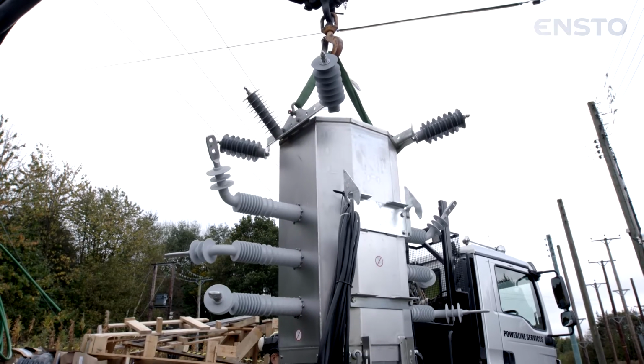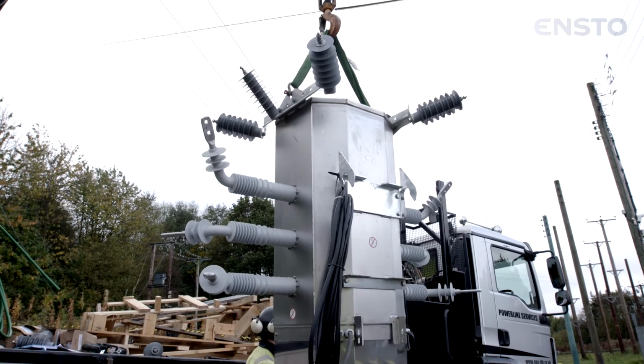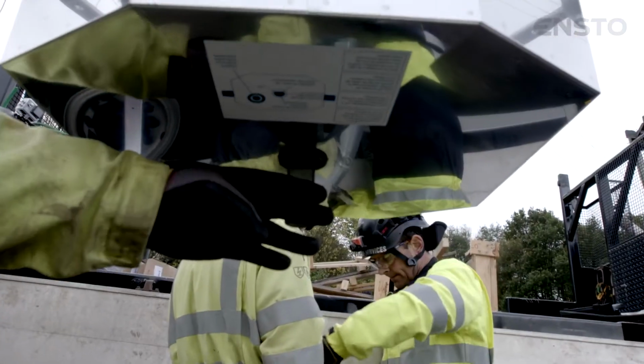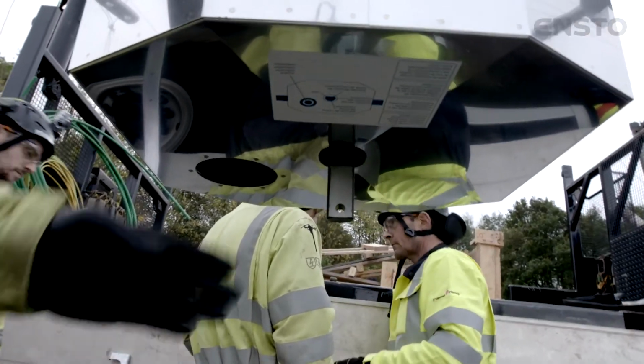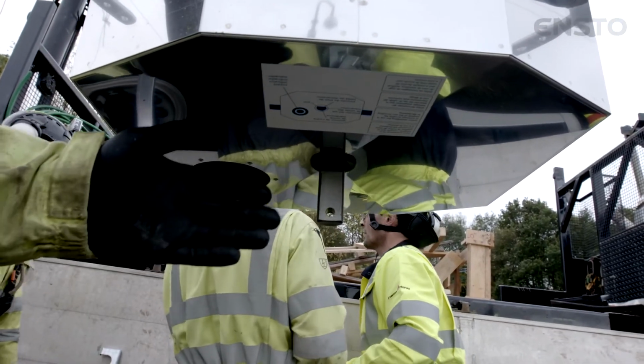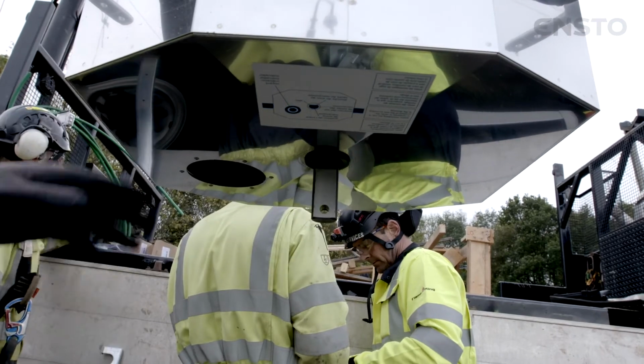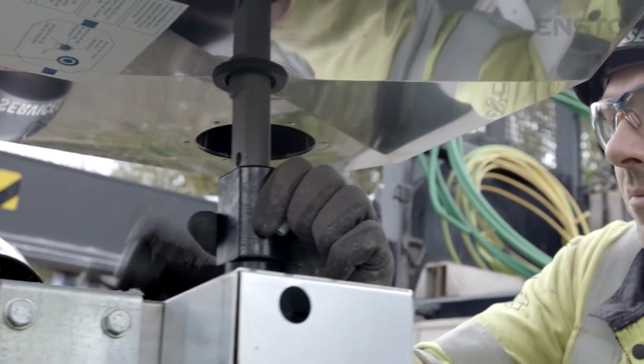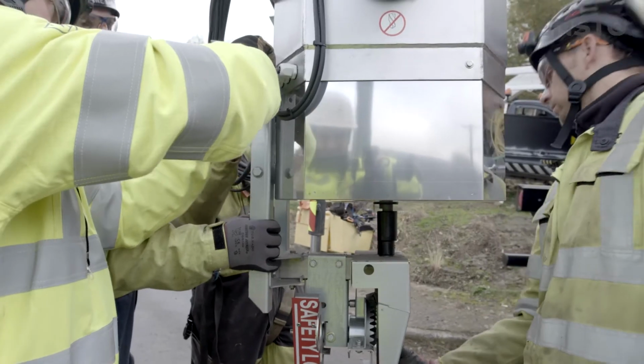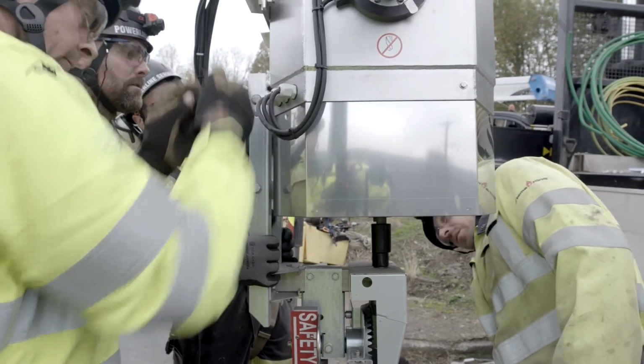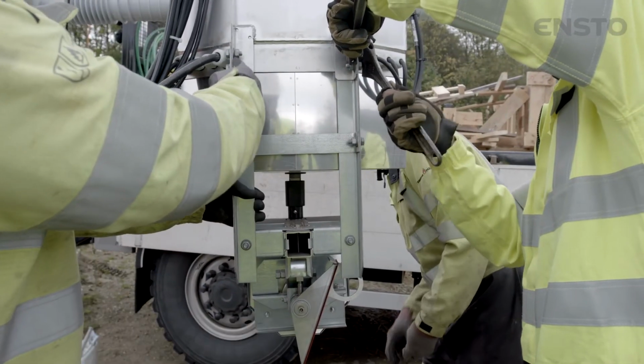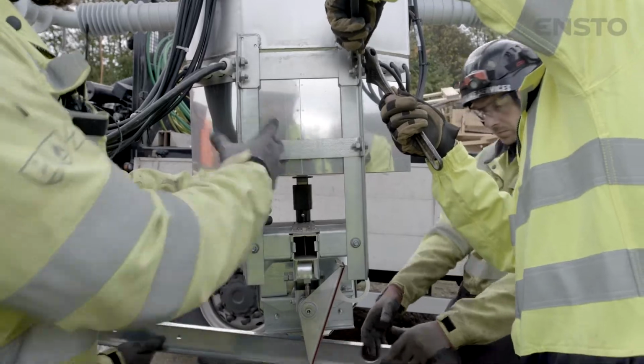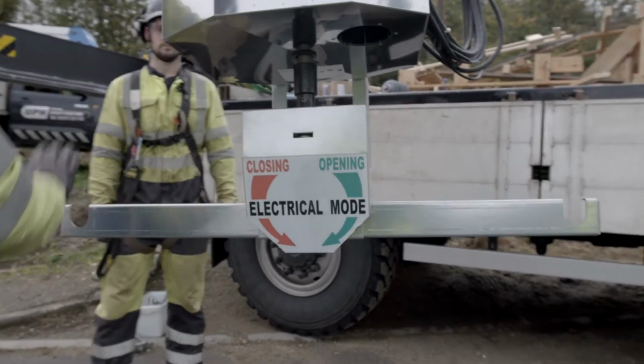Once the 6 surge arrestors are attached, we can proceed to mount the manual operating mechanism. Begin by ensuring the switch is in the electrical position. The flat edge should be facing forward. This will then align with the mechanism as it is introduced. There are 4 bolts on the supporting bracket. The operating arm requires 2 bolts and shall be mounted horizontally.